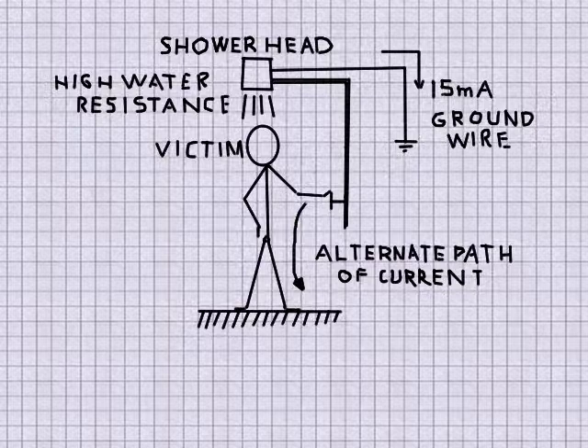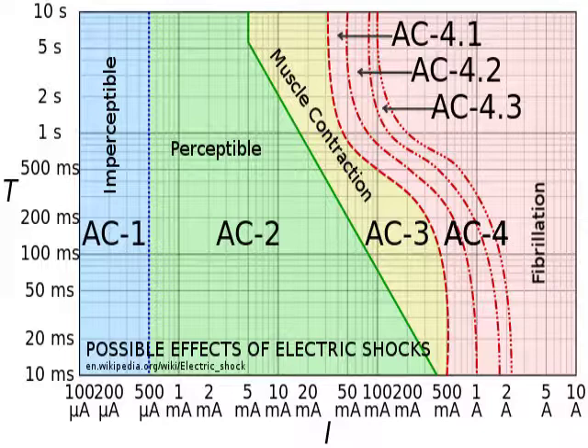We showed that a current up to 15 milliamperes can flow through the ground wire when it is connected to the mains ground. If the ground wire fails, it could flow by whatever alternative means available. The human skin is not a short circuit, but this figure represents the order of magnitude of the risks involved. According to this graph, 15 milliamps flowing from your left hand to your feet is not enough to cause death by fibrillation, but it is perceptible and can cause muscle contraction if you get exposed for more than 1 second. It is a harsh discomfort you should not be experiencing at a time so relaxing as a good hot shower must be.